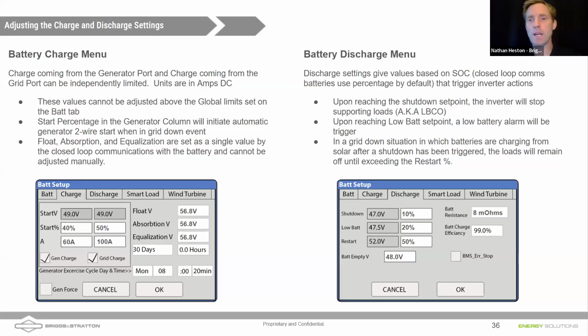The Sol-Ark will beep at you if you've got beep enabled, to just let you know, hey, you're getting towards a low battery situation. And the restart percentage is the percentage at which, if you're in a grid down situation and the batteries have reached the low battery shutdown percentage and shut off loads, they have to be able to charge back to a certain point. So if they're charging back off of solar, we're not going to turn it on immediately when we hit 10%. We're going to turn it on when we hit this restart percentage. Depending on how big your solar array is, you might want to charge those batteries up more before you turn the loads back on, so you don't have the loads turning on and off multiple times in a day. And then the battery empty voltage is a reference point at which the battery is considered empty from the battery perspective. For a 6.6 battery, that should be set at 48 volts.